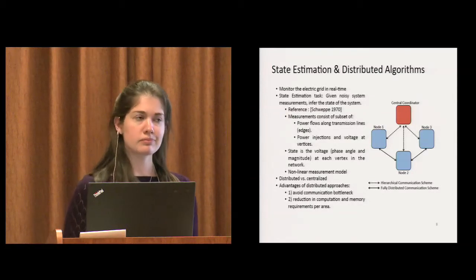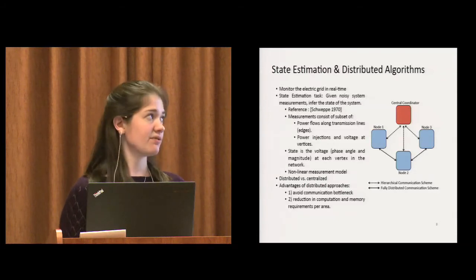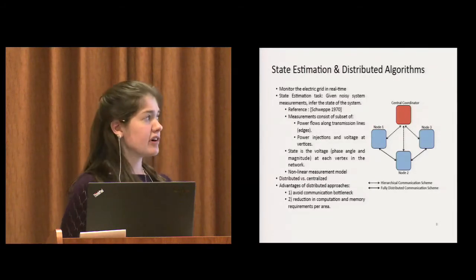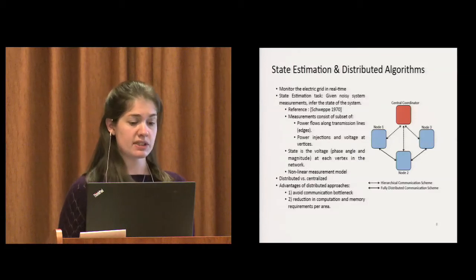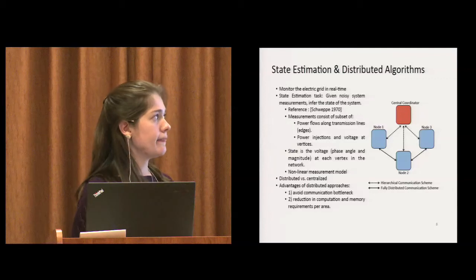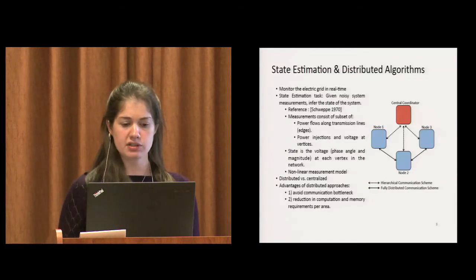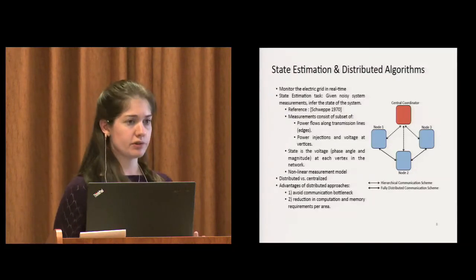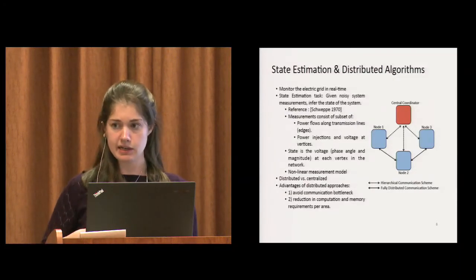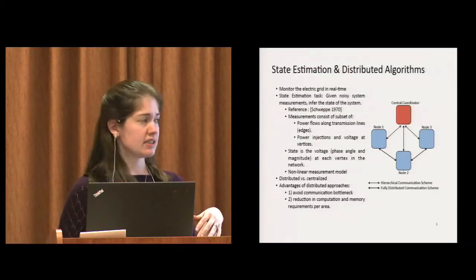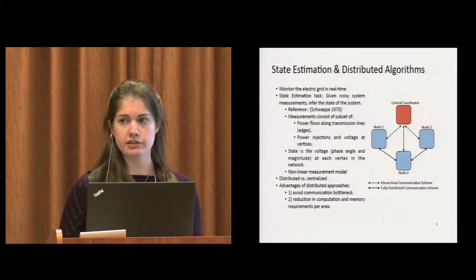This is an important problem in power systems studied as far back as 1970 by Schweppe. For us, our measurements consist of some subset of the power flows along transmission lines and the power injections and voltages at vertices. The state of the power network is the voltage at every single vertex in the network. The measurements are related to the state by a set of nonlinear equations.